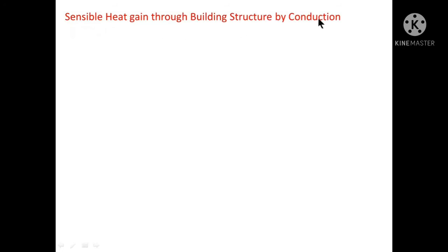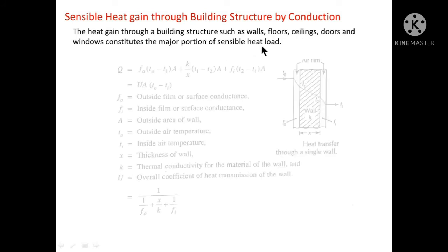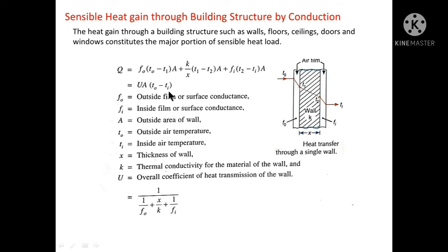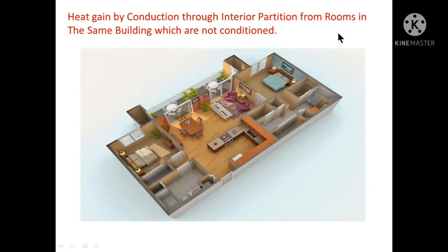Sensible heat gained through building structure by conduction: the heat gained through building structures such as walls, floors, ceilings, doors and windows constitutes the major portion of sensible heat load, which is given by Q = U·A·(To − Ti). This formula can be utilized for calculation of heat transfer through walls, floors, ceilings, doors, windows, etc. Next is the heat conducted through interior partitions from rooms in the same building which are not conditioned — heat can enter a space from other rooms in the same building.